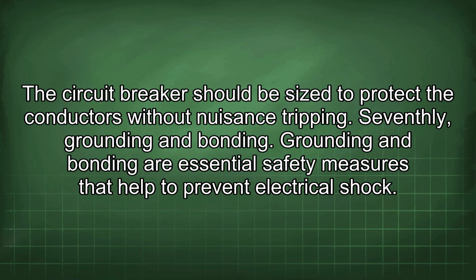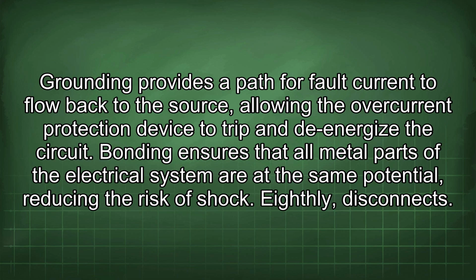Seventhly, grounding and bonding. Grounding and bonding are essential safety measures that help to prevent electrical shock. Grounding provides a path for fault current to flow back to the source, allowing the overcurrent protection device to trip and de-energize the circuit.